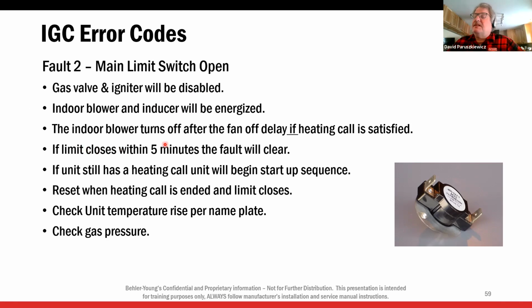Okay. If limit closes within 5 minutes, the faults will clear. So if the limit closes within 5 minutes, it will clear and will continue our cycle. If the unit still has a heating call, it will start up its startup sequence again. It will reset when the heating call is ended. So if we recycle the thermostat, if we're having limit trips or if we've had a limit trip, first thing, check temperature rise. That's the first giveaway. We're going to talk about that in a second. And then, of course, checking gas pressure.